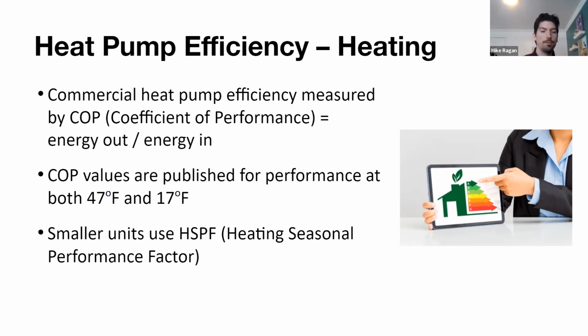Now, smaller equipment, these would be more your mini splits and your multi splits. They also publish heating efficiencies in what's called HSPF, or the heating seasonal performance factor. That's a metric that's used as well to differentiate between heat pump models for smaller heat pump systems. Again, that's mostly going to be in single phase equipment, residential or light commercial.